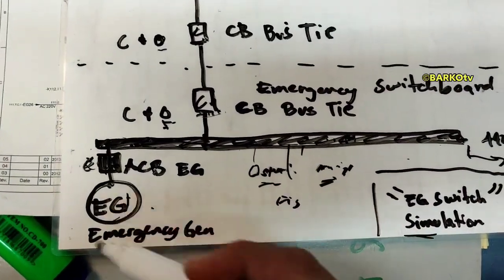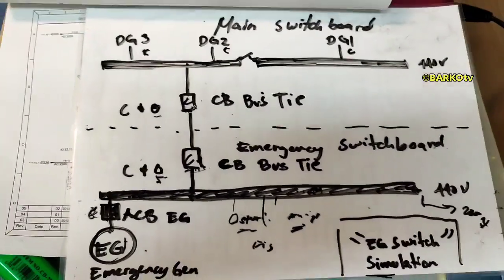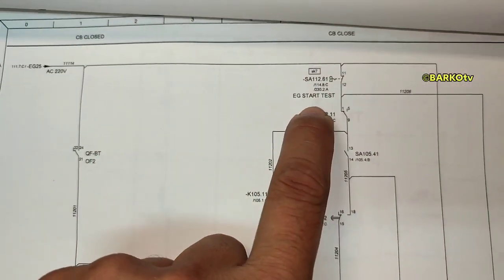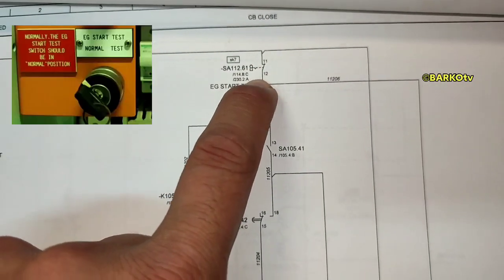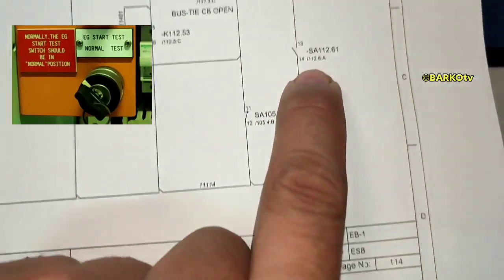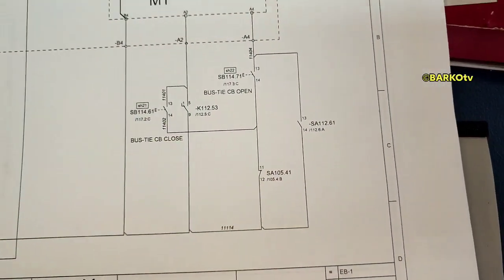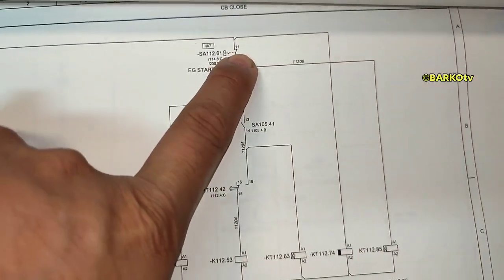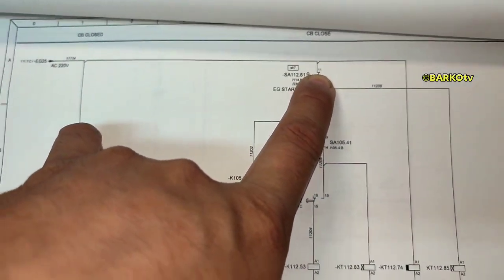Now let's go to the manual. This is the emergency start test — contacts 11 and 12, reference 61. The next contact is SA105.41, terminals 13 and 14. If you test that, this will open the bus tie and the CB will close.